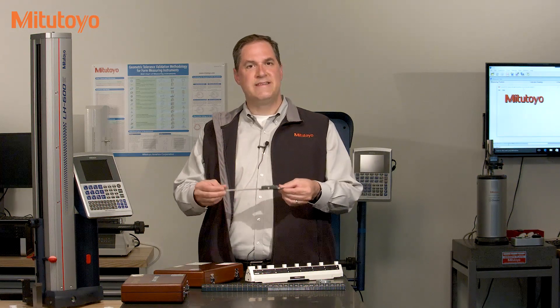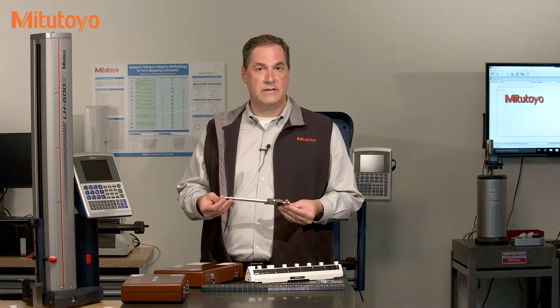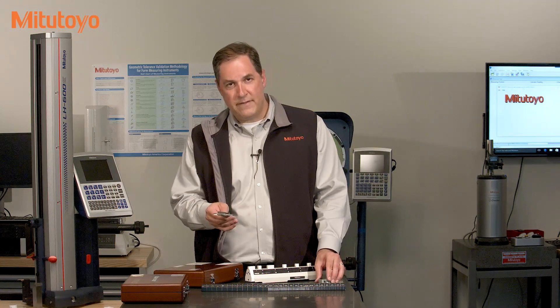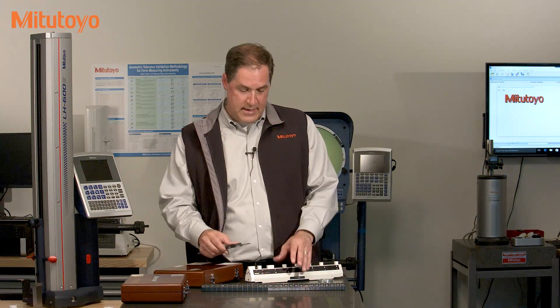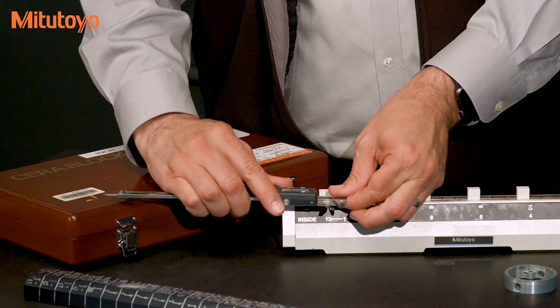But how exactly are the measurements made using this caliper traceable to the meter or inch at NIST? Let's walk through an example. Say this caliper is used at some manufacturing organization and they calibrate this caliper themselves in-house using a caliper checker, something like this.